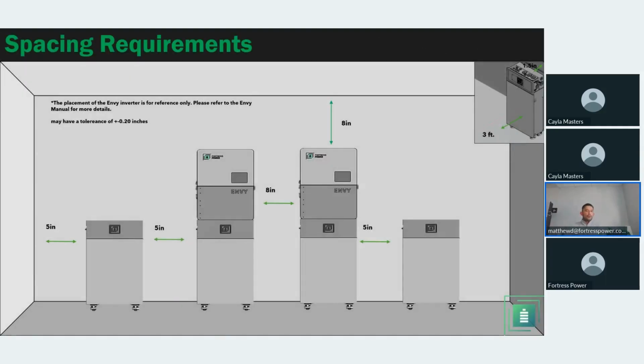These are some spacing requirements per the UL certification that will be released October 31st. What we require is that each battery is spaced about 5 inches apart, and the inverter 8 inches if you were to parallel ENVI with ENVI, just for better heat dissipation. Then have a clearance of 3 feet in front of it, and 1.5 inches from the battery to the wall, which is already done for you, since we include some brackets to install against the wall, so you don't have to do that measurement.